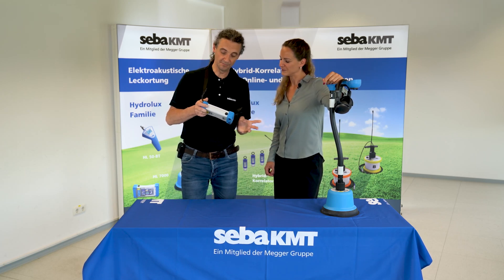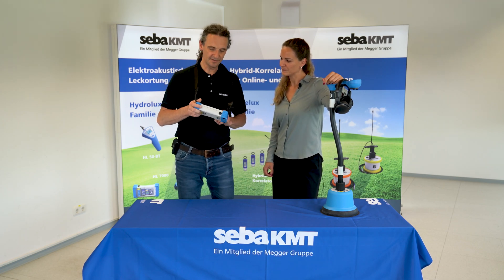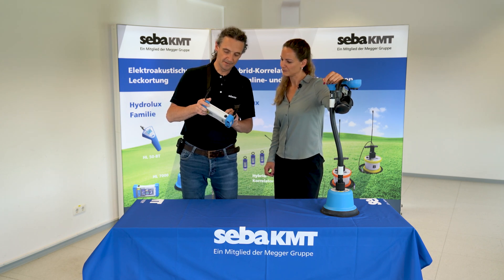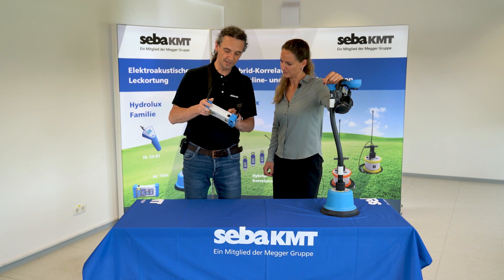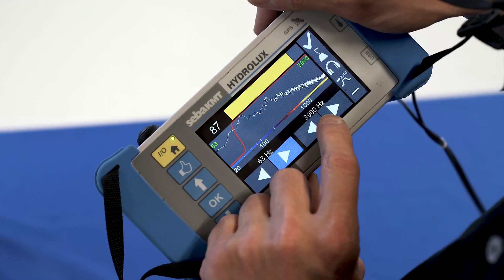If I don't like that, for example because of background noise, or because I'm sure what material the pipeline I've been listening to is made of, I can adjust the lower limit frequency with the left arrow keys or the upper limit frequency with the right arrow keys.